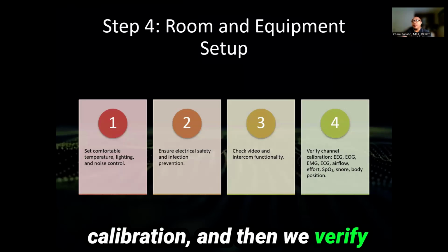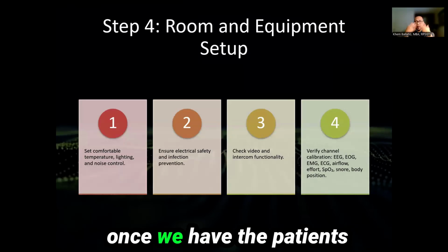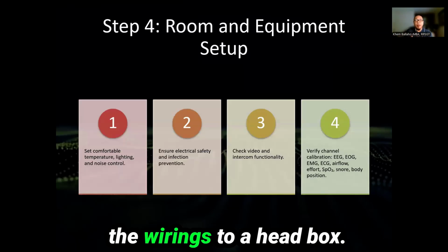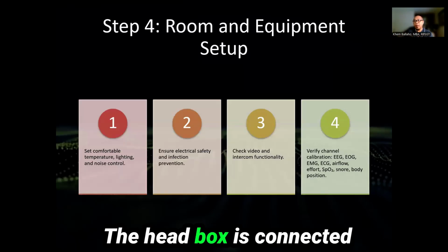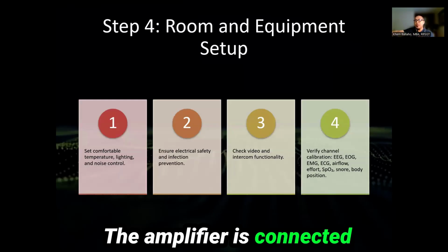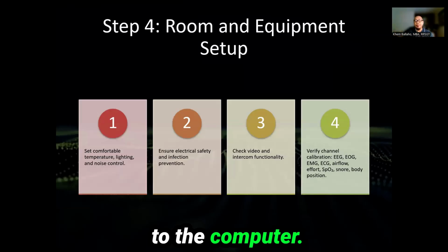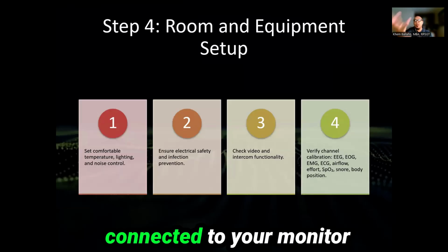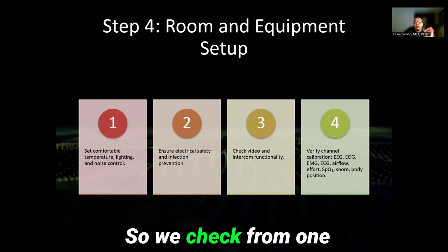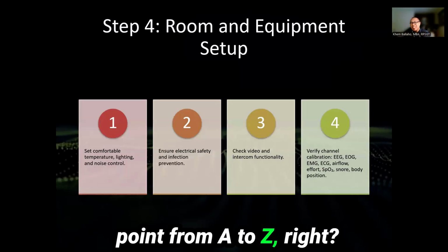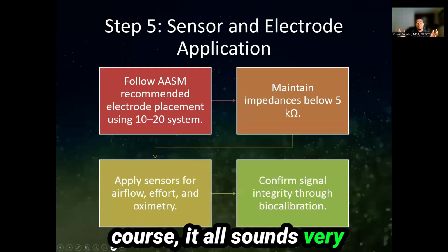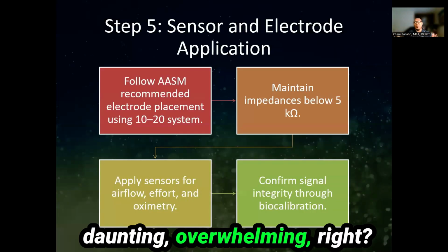And then we verify all channels and the sensors once we have the patients connected to the sensors, right? And then we connect all the wirings to a head box. The head box is connected to the amplifier. The amplifier is connected to the computer. Okay, and from the computer, it's connected to your monitor so you can see everything. All right. So we check from one point from A to Z. All right. That's our job as sleep techs. Of course, it all sounds very daunting, overwhelming, right?